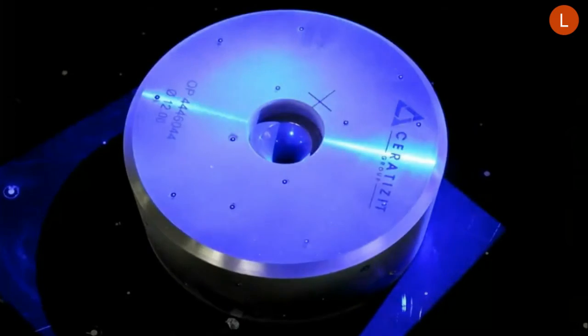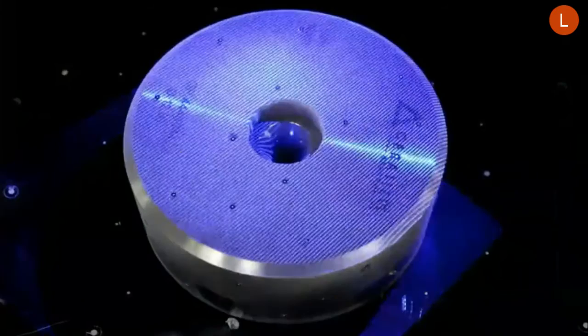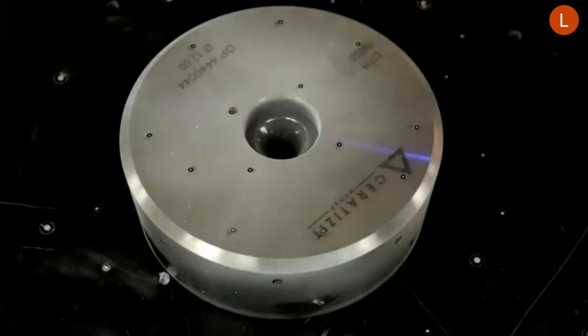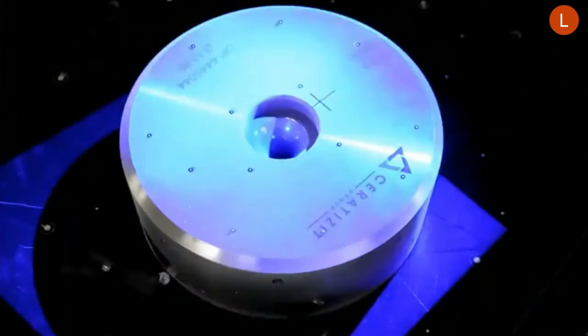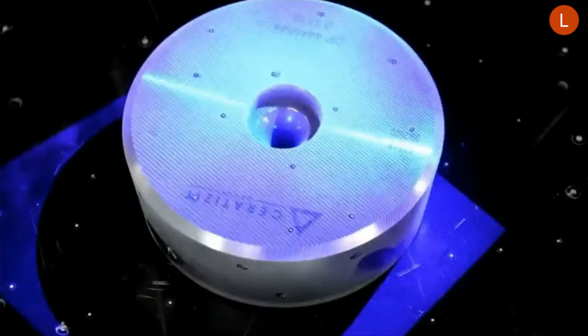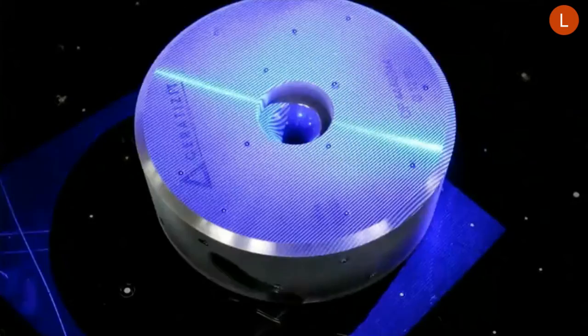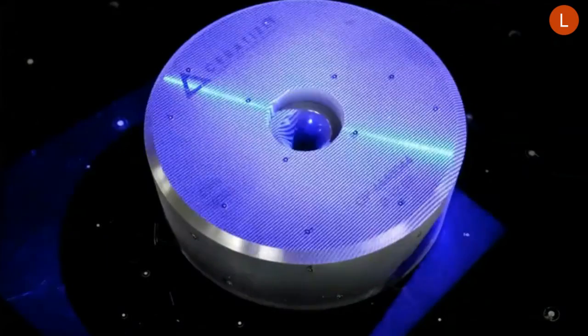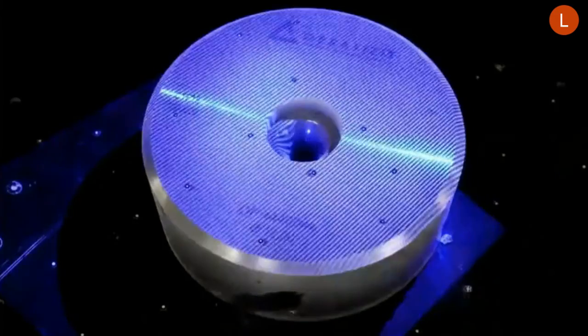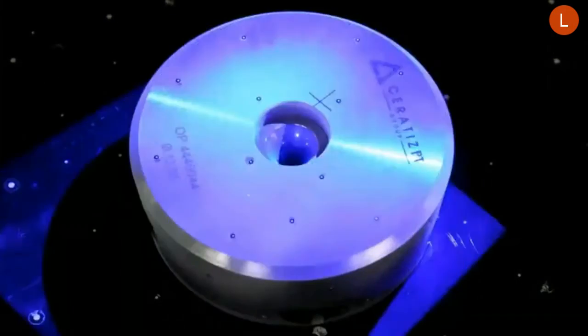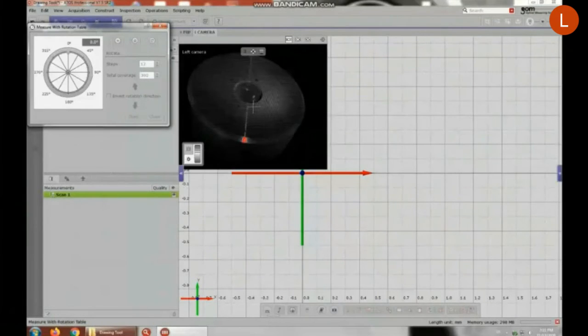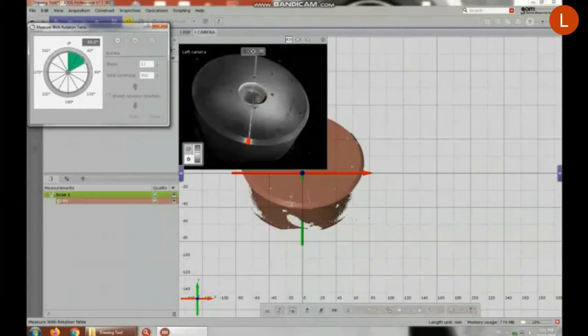The scanning head projects different fringe patterns onto the scanned object's surface. These patterns are recorded by two CCD cameras, left and right, forming a phase shift based upon sinusoidal intensity distributions on the CCD sensors. The ATOS 3D scanner uses multiple phase shifts in a heterodyne principle to achieve highest sub-pixel accuracy. Based on the optical transformation equations, independent 3D coordinates are automatically calculated for each camera pixel. In the case of the ATOS 3D scanner, a point cloud of up to 5 million surface points results for each measurement.